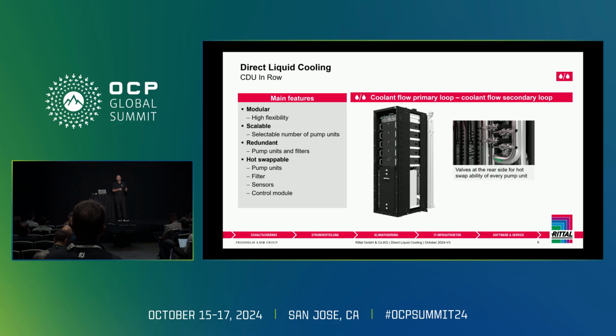And then going from that extreme to the other, which is our full Inrow solution. This is a 1 megawatt solution. It's highly modular, highly flexible. So at the base of it, you can see it's a disaggregated CDU. It is a very large heat exchanger at the base and 5 pumping units. And those 5 pumping units have got the capability of pumping around 250 kilowatts of cooling capacity each. And as you can see, 4 times 250 is a megawatt, leaving one as a redundant unit. And of course, that can also be scaled. It's also within the form of an ORV3 rack. Incredibly compact and incredibly modular.